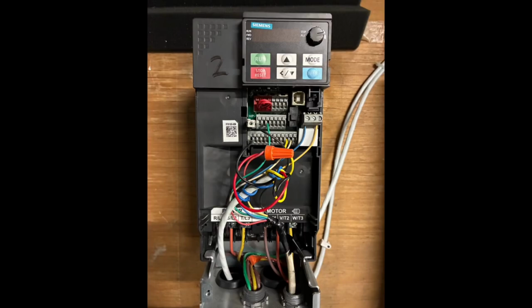So it goes to our programmable digital timer switches, then back into the VFD, and that's what that black wire is, coming from that programmable digital timer. And of course I had to land another 24 volt negative wire on the common terminal there that you see next to the white wire.